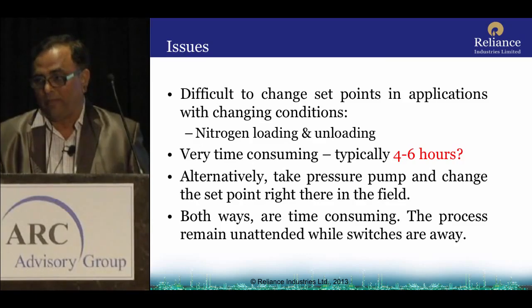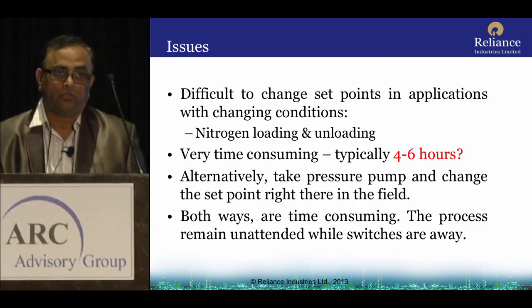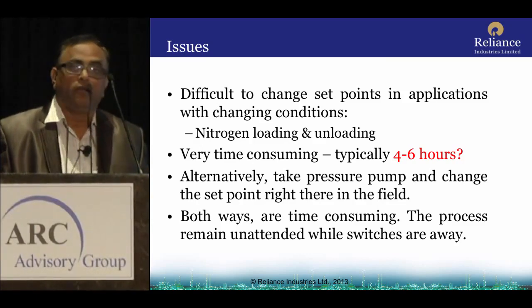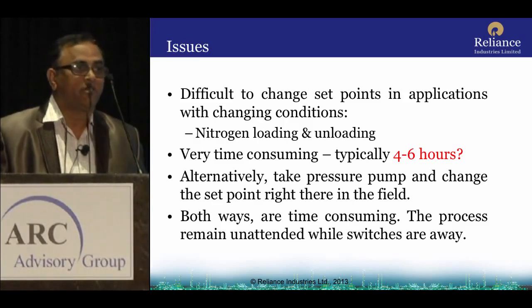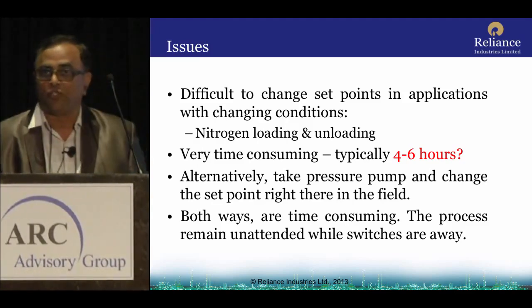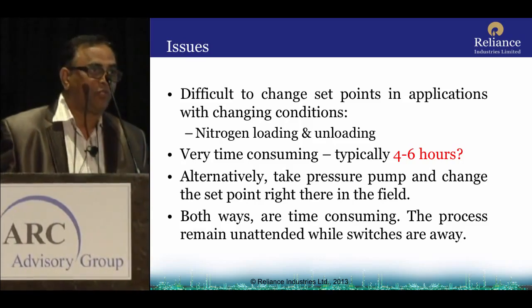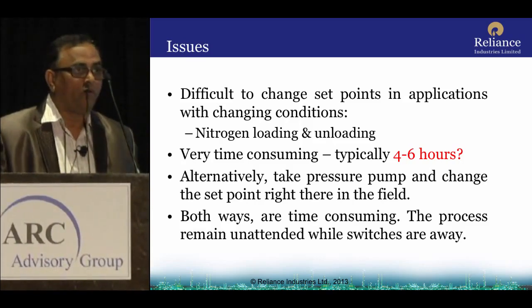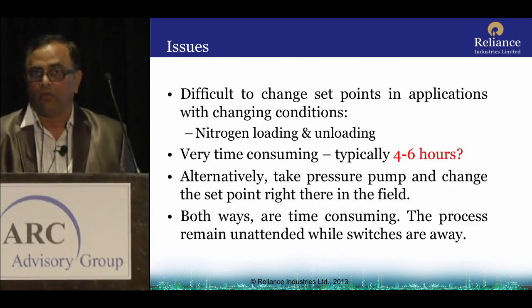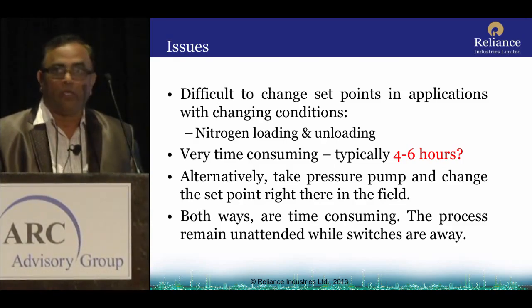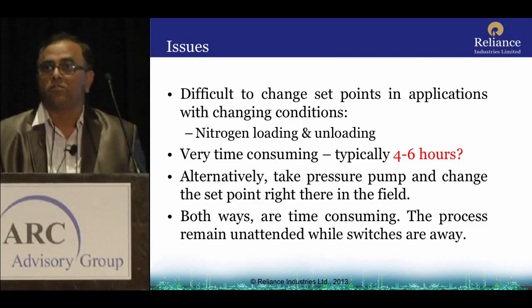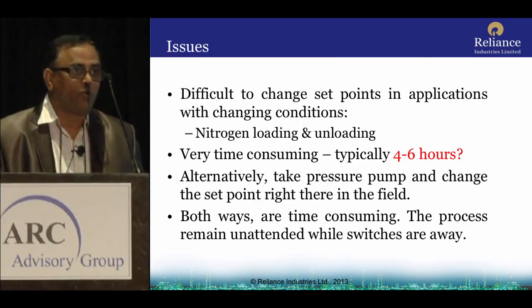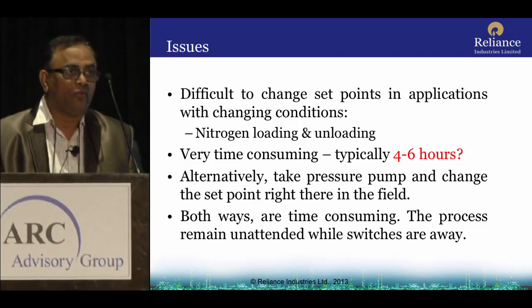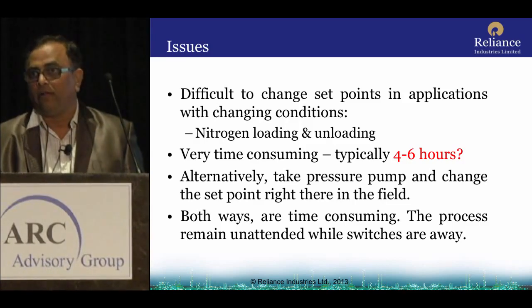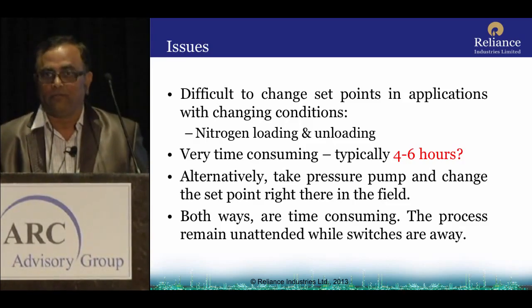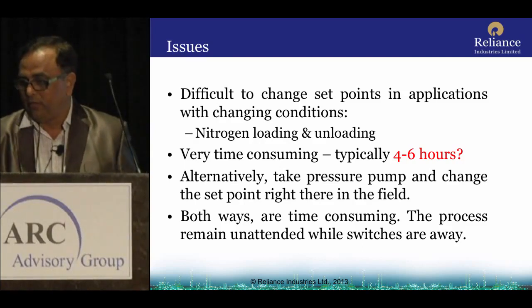It is difficult to change the set points in the application with changing conditions. We have some applications where maybe for 6 hours I want to run my machine at a particular set pressure, and again 4 hours at another set pressure. Now, with electromechanical switches, it is very difficult to change over the set points in the field itself. Either you have to take the pressure pump into the field and do the calibration, which takes a hell of a time.